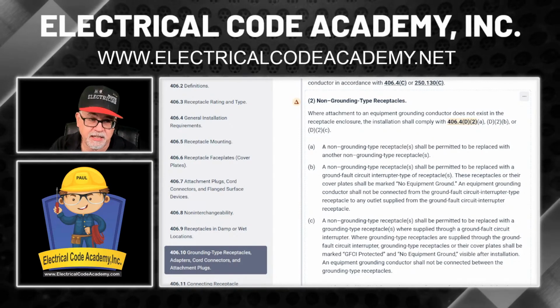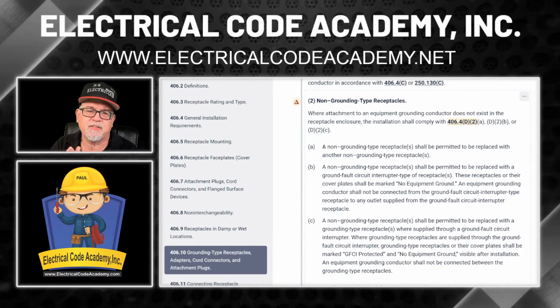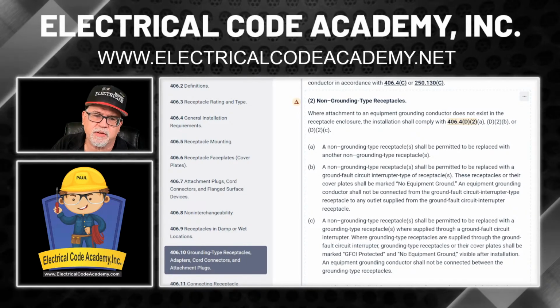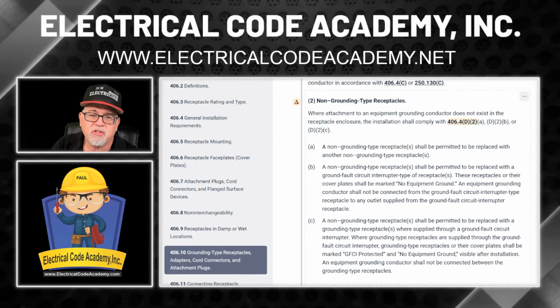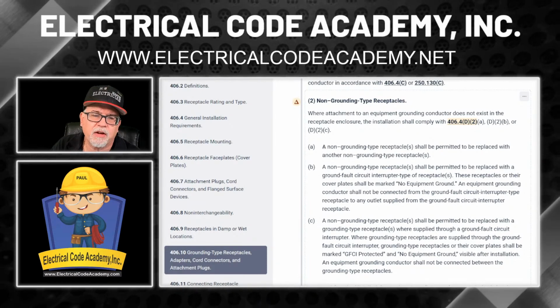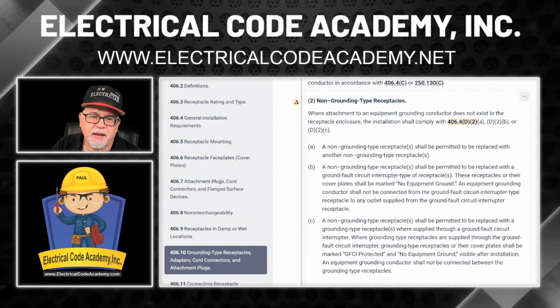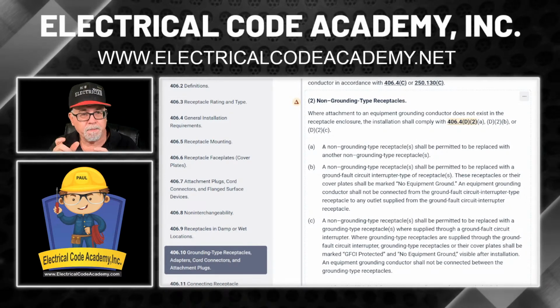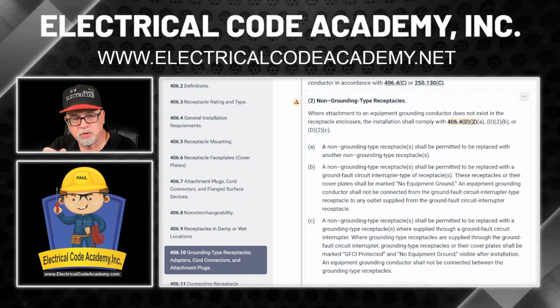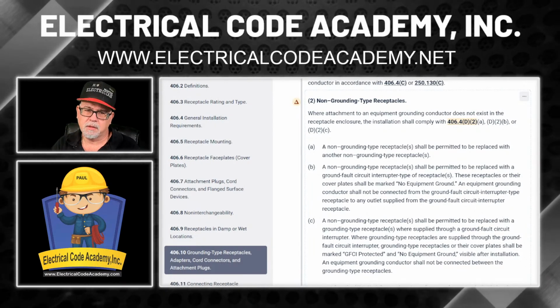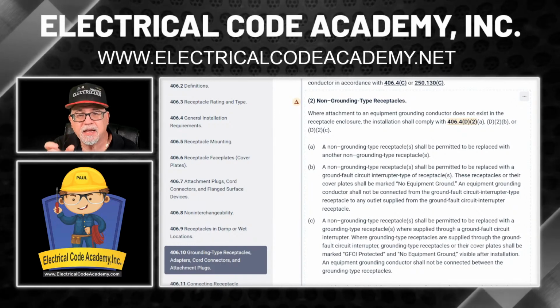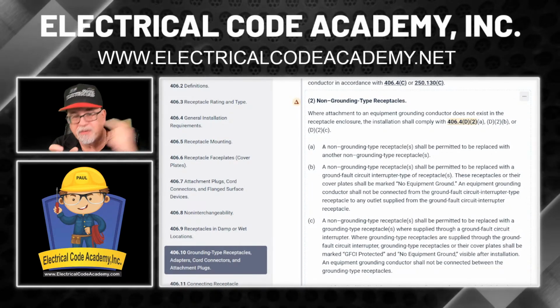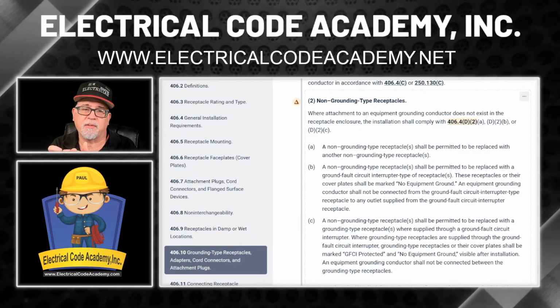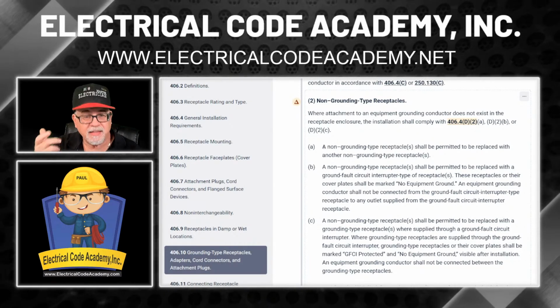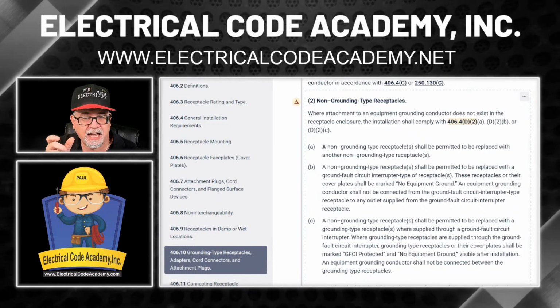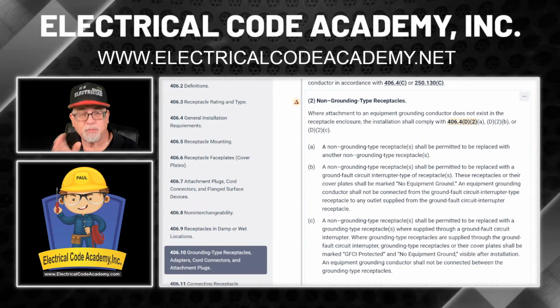So the little difference in this one is, let me read it to you. We're at C now. It says, a non-grounding type receptacle, kind of what was there, the 2 prongs, shall be permitted to be replaced with a grounding type receptacle where supplied through a ground fault circuit interrupter. So when it says supplied through, that means I take the 2 prong out, I put the 3 prong in, the grounded type, and if I have a GFCI circuit breaker, it's protected through that circuit that's supplied from that GFCI circuit breaker. That's what it means, supplied through the GFCI device. Okay, so that's what that means.